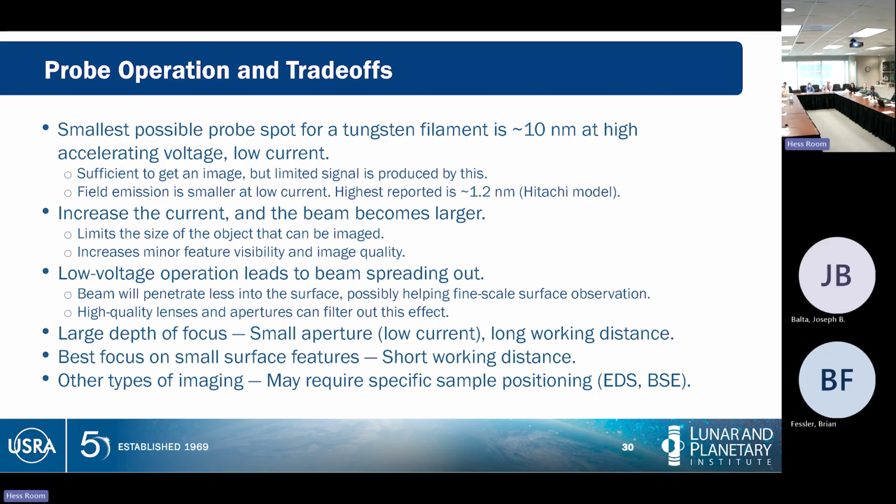These are some of the operating trade-offs that come just out of the design of the SEM. Control the current, control the voltage, control the lenses. That can give you different beam sizes, different penetration depths, different types of interactions with the sample. Specific types of imaging, EDS mapping, backscattered electron mapping, will then pop out of this and be influenced by these settings.